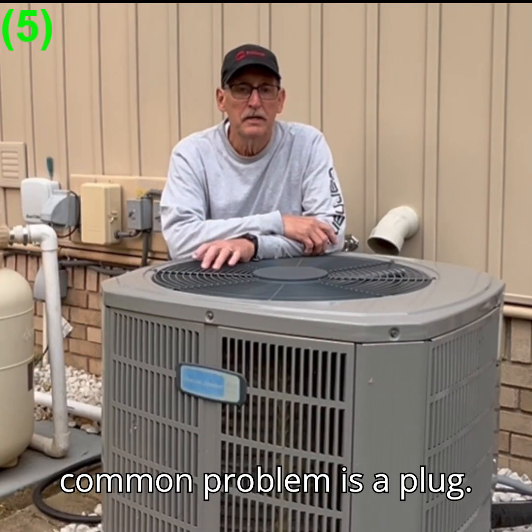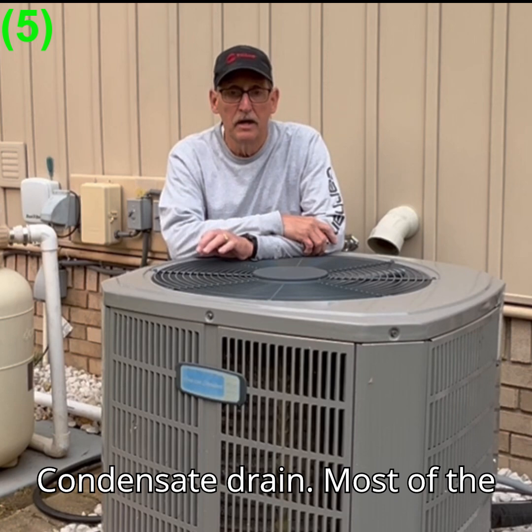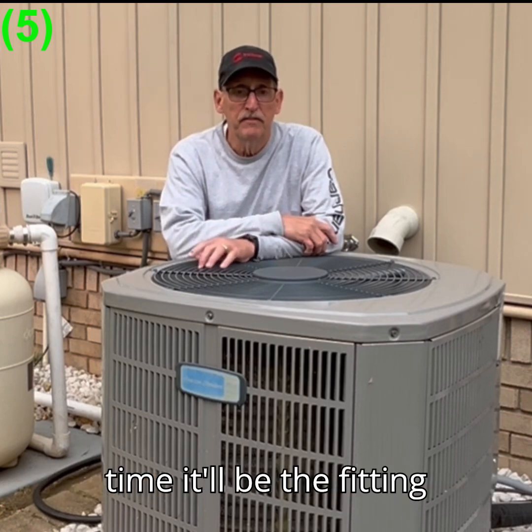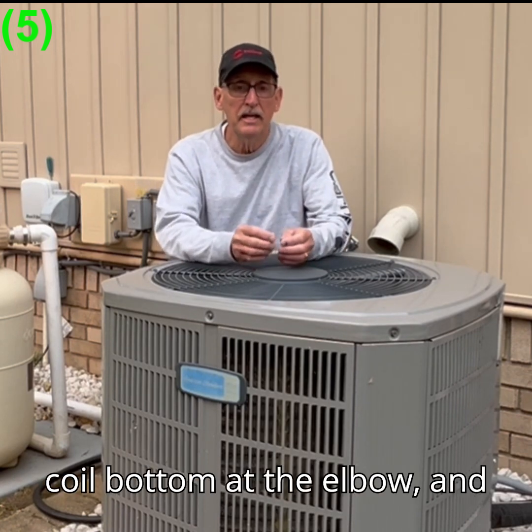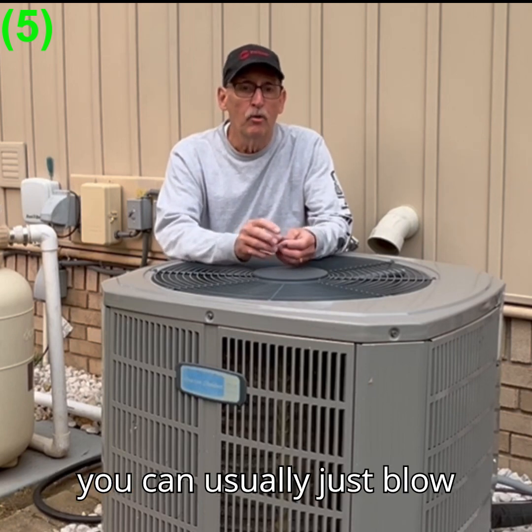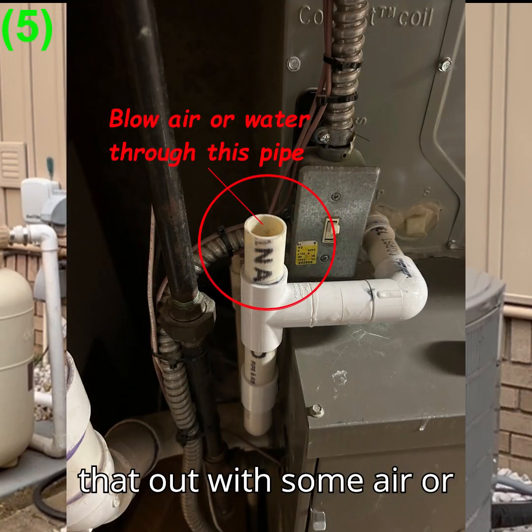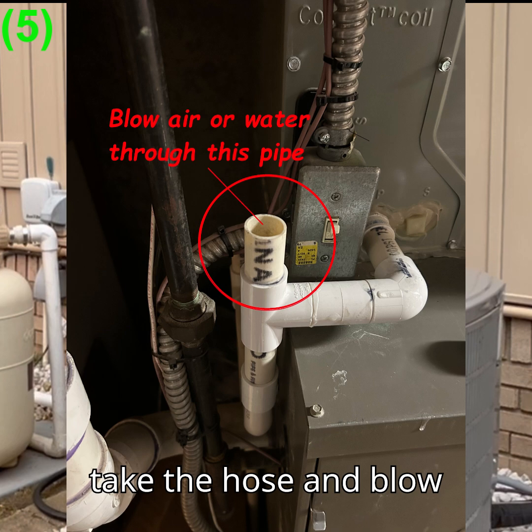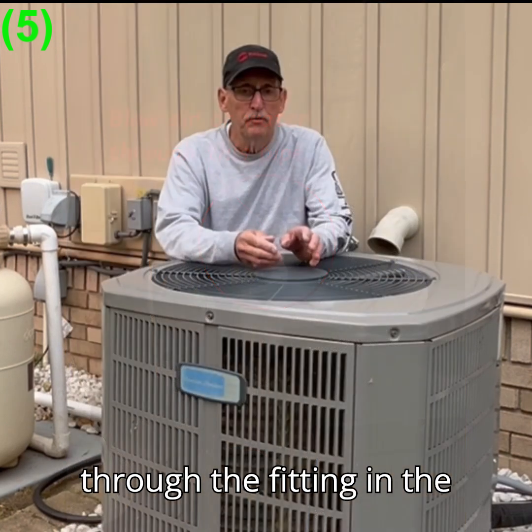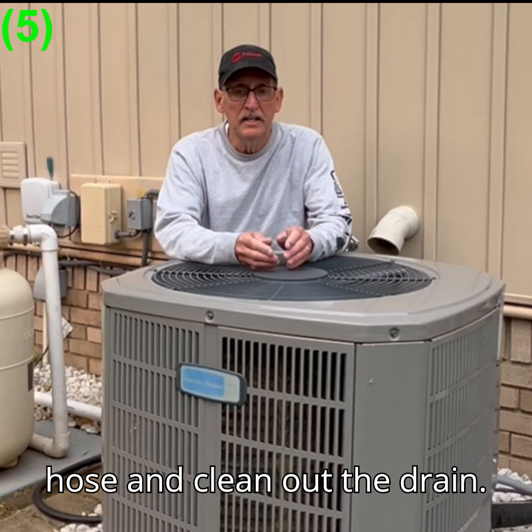Another common problem is a plugged condensate drain. Most of the time, it'll be the fitting that's plugged into the A-coil bottom at the elbow, and you can usually just blow that out with some air, or take the hose and blow through it. Either way, blow through the fitting and the hose and clean out the drain.